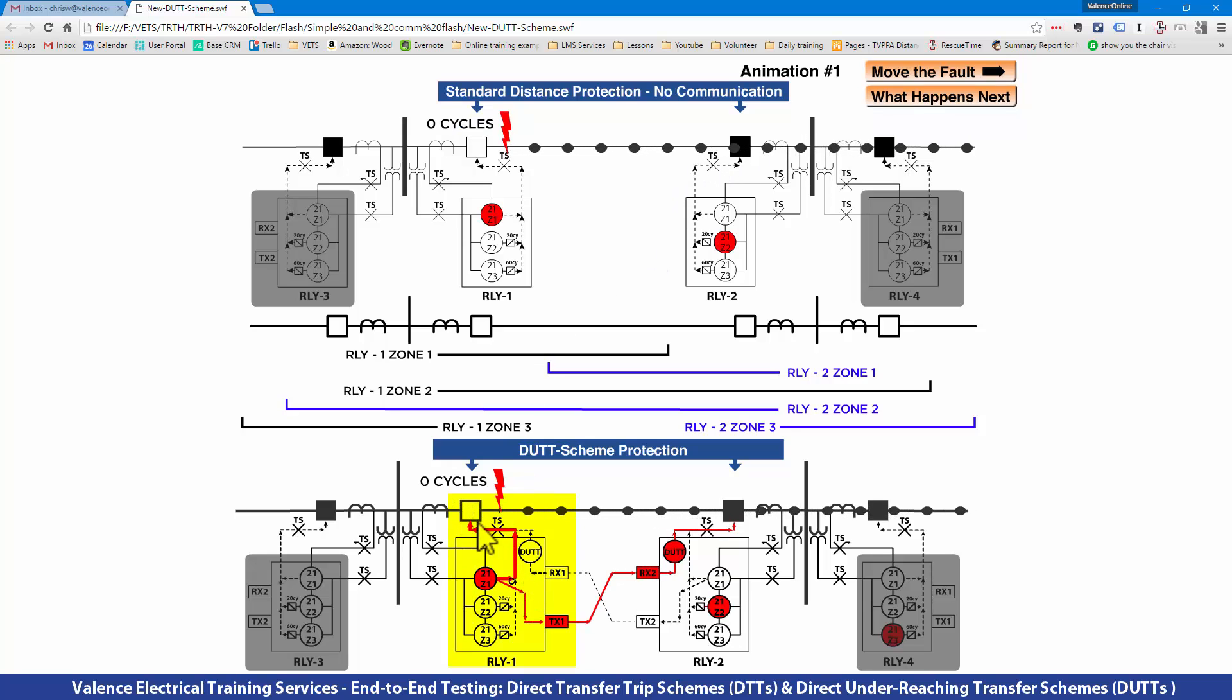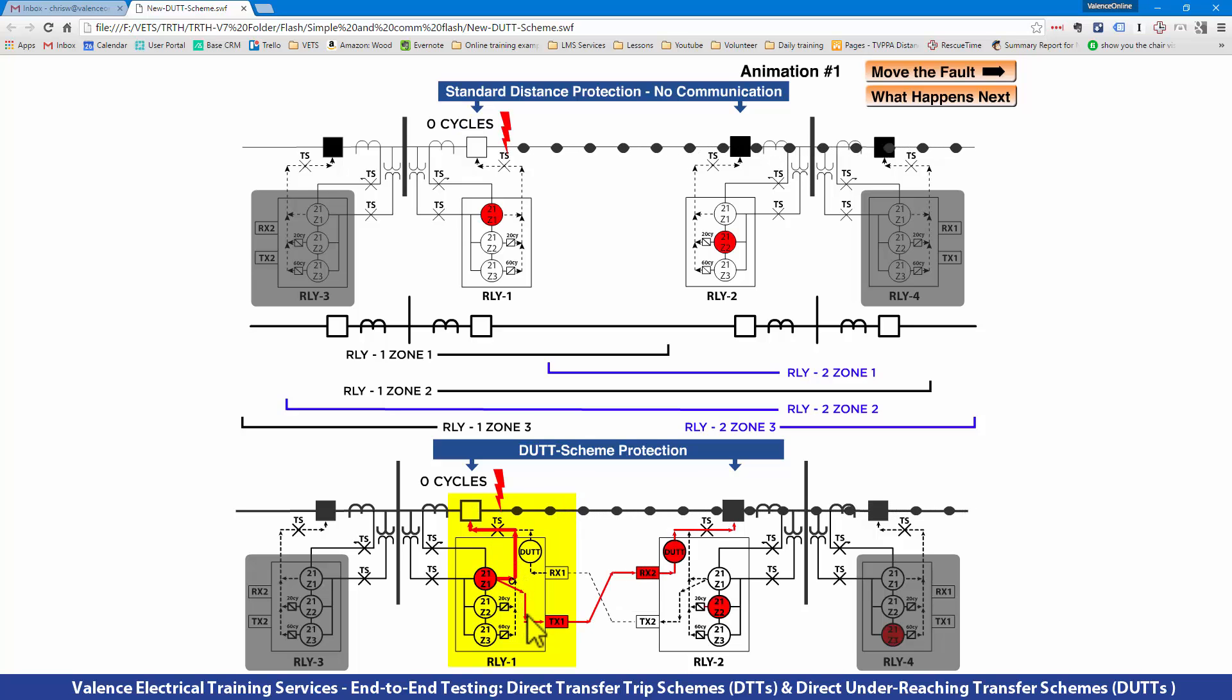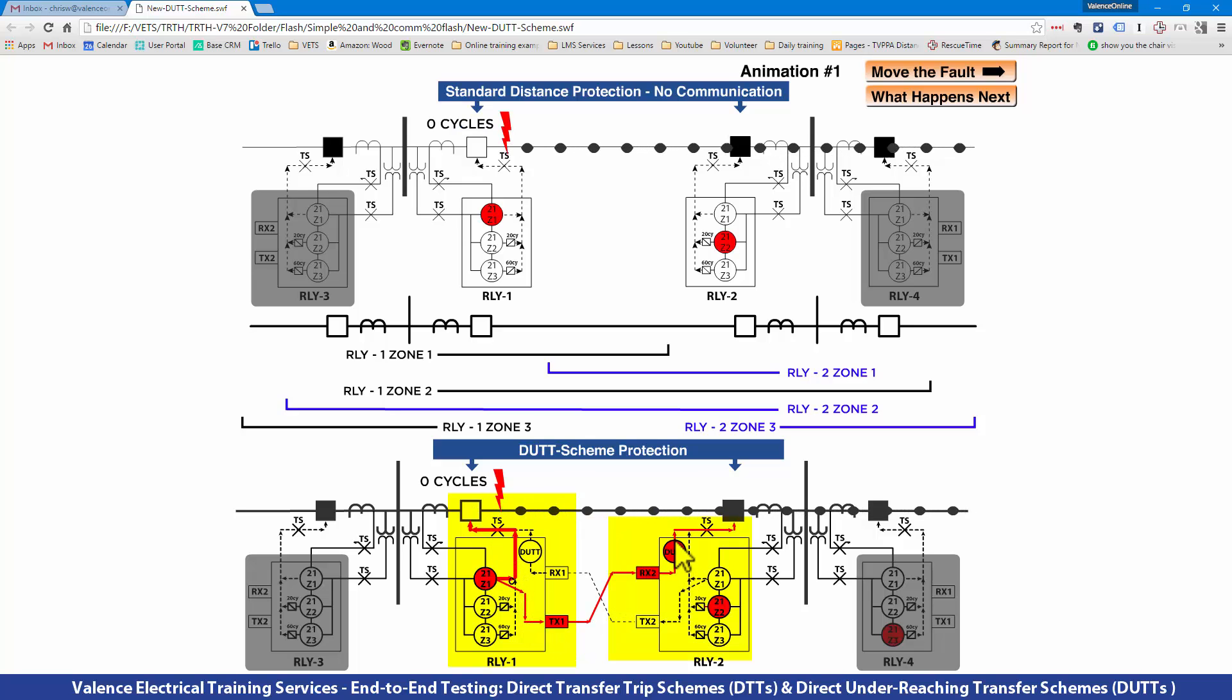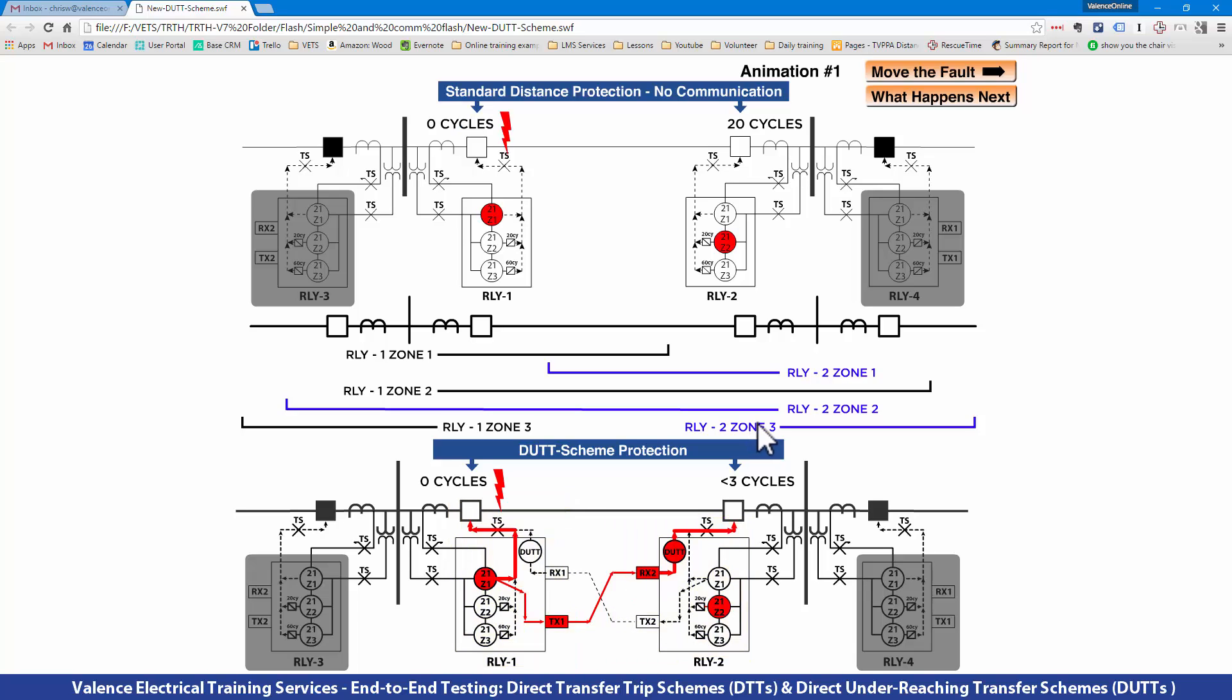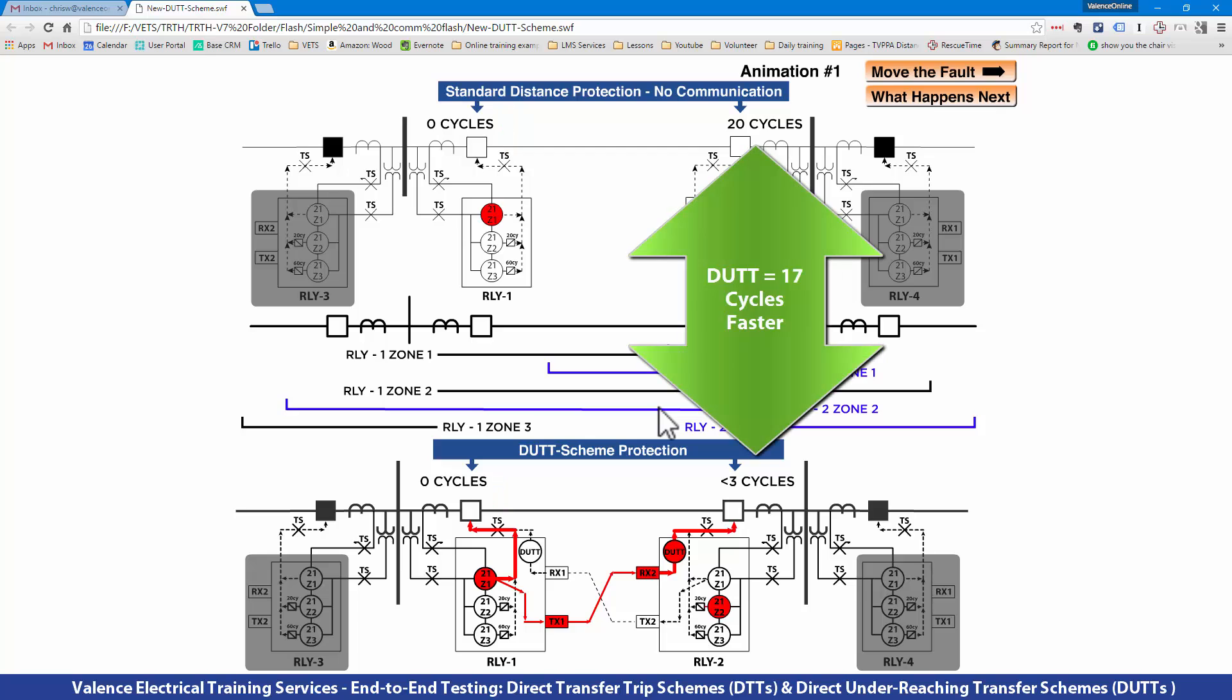Zone 1 still trips the Relay 1 breaker immediately, but it also sends a command to the other side telling it to open as fast as it can, which is typically under three cycles depending on communication delays. The DUTT scheme has saved us 17 cycles.